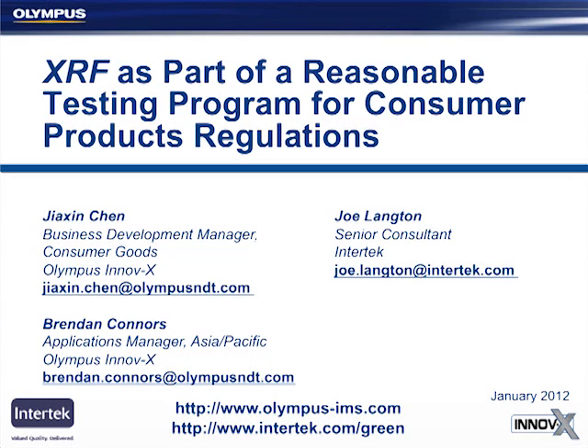I see a good question on what's the main difference in operation between an isotope scanner XRF equipment with cobalt-57 source versus an X-ray tube. I only talked about X-ray tube XRF in this talk. It is also possible, instead of using an X-ray tube, to use an isotope source to produce your X-rays. There are a few drawbacks to using an isotope source. You actually have a radioactive material in your analyzer, which means there's, in most states and most countries, a different set of regulatory requirements that you have. There are, in some cases, greater restrictions on travel with the analyzer, and there are some disposal concerns with using an isotope source.